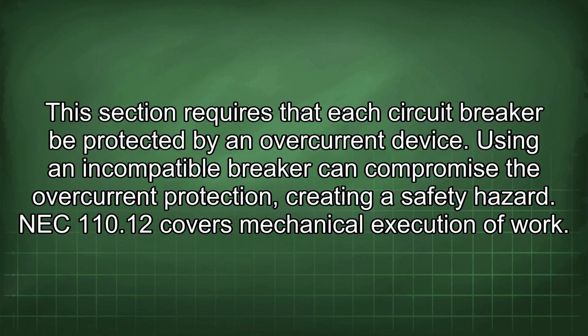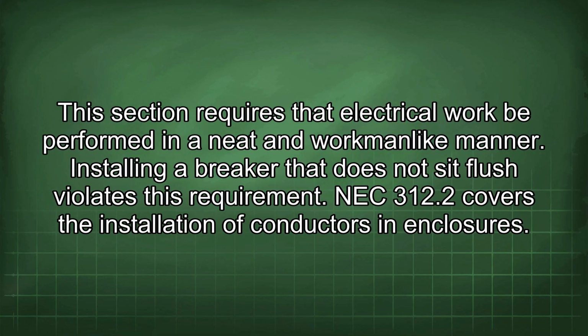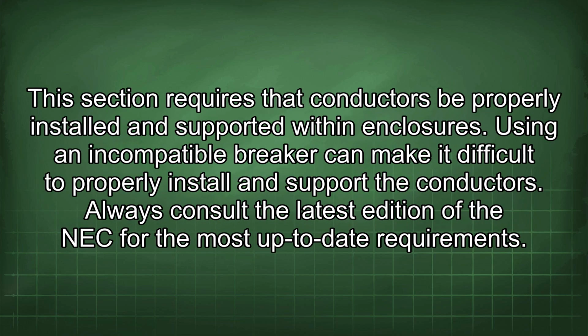NEC 110.12 covers mechanical execution of work. This section requires that electrical work be performed in a neat and workmanlike manner. Installing a breaker that does not sit flush violates this requirement. NEC 312.2 covers the installation of conductors in enclosures. This section requires that conductors be properly installed and supported within enclosures. Using an incompatible breaker can make it difficult to properly install and support the conductors. Always consult the latest edition of the NEC for the most up-to-date requirements.